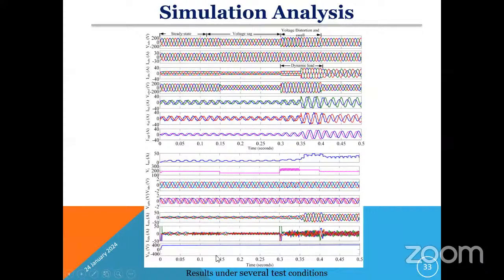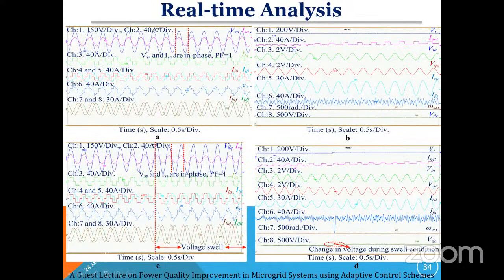And see, these are some few important experimental results. See the voltage VSA and current ISA, both are in phase. Both are in phase means the power factor is unity. In the previous case also I explained the same thing. If voltage and current are in the same phase, then your power factor is 1, that is unity. Otherwise, your power factor will be lag or lead. So we have to maintain the power factor at unity. Then only can we send the maximum power from the photovoltaic system or from the renewable energy sources to the local loads or to our utility grid.